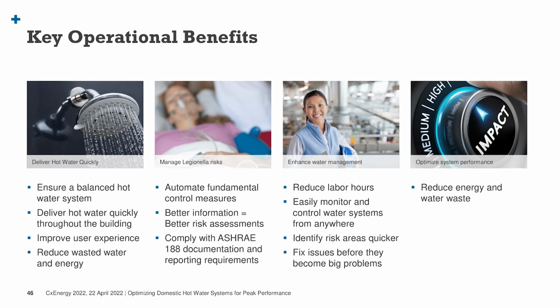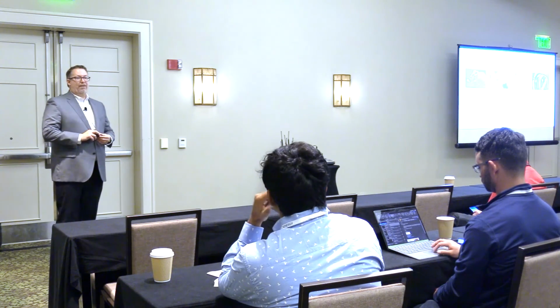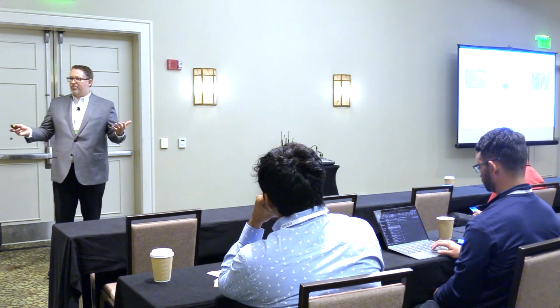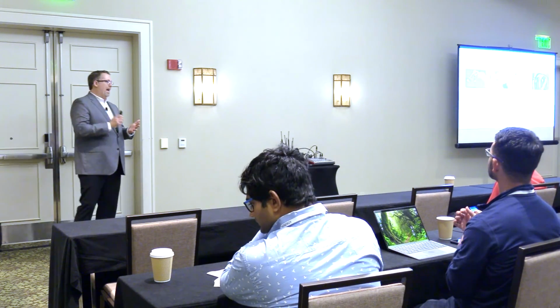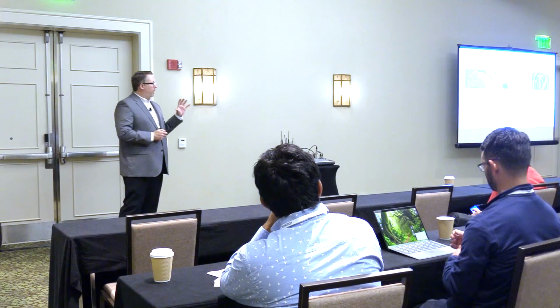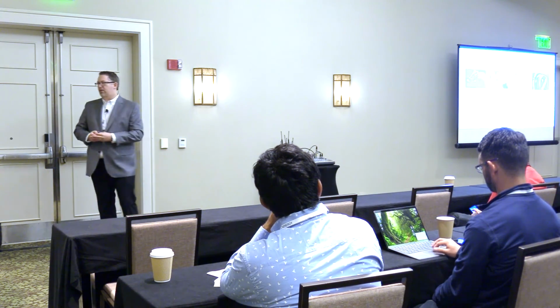Some of the key operational benefits of using automated systems, particularly on your domestic hot water balancing, is that you're delivering hot water quickly, managing those risks of Legionella. Temperature control, or maintaining temperatures, is one of those key fundamental control measures for managing bacteria growth. It also enhances water management for facilities, like healthcare facilities, that are required to have an ASHRAE 188 compliant water management program where they have to identify control measures, do monitoring, and reporting. Having a digital or automated system gives them extra benefit.